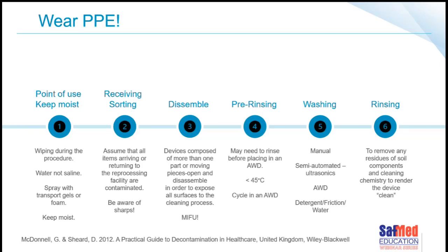The number of times I've been to a theatre or a CSSD complex and the artery forceps are still on the stringer, closed, and in the washer like that. I'm not sure. And the excuse is that, well, they never looked like they used those ones. Really? Yes. Right, the instructions for use may call for pre-rinsing, and that could be something that's part of the initial cycle in the washer. It could be something that you're doing at the basin. Remember, then you want the temperature of the water to be less than 45 degrees. Why? Because if you've got a whole bunch of proteins on an instrument and you use hot water to rinse it, you're going to bake on the proteins, and it becomes harder to remove them later.